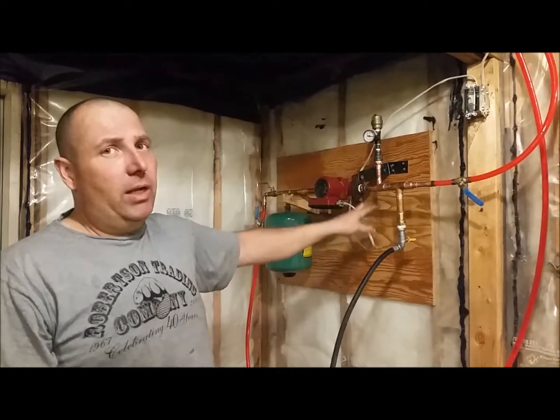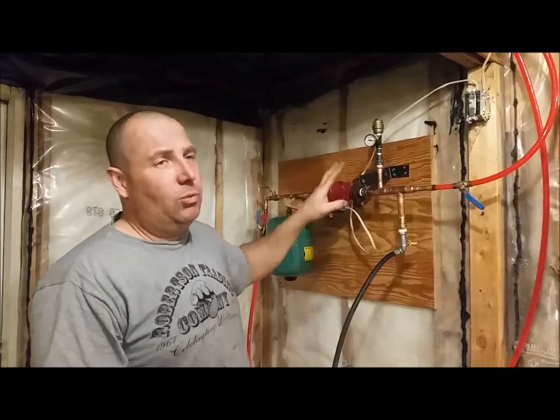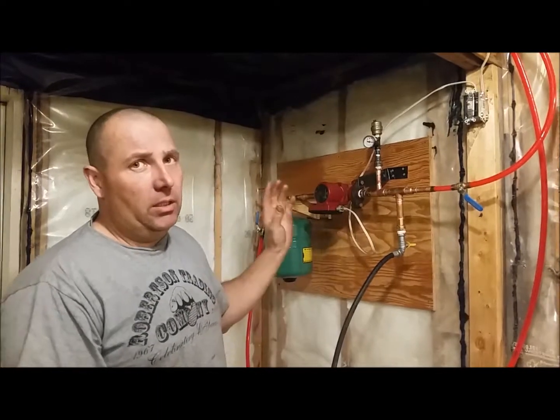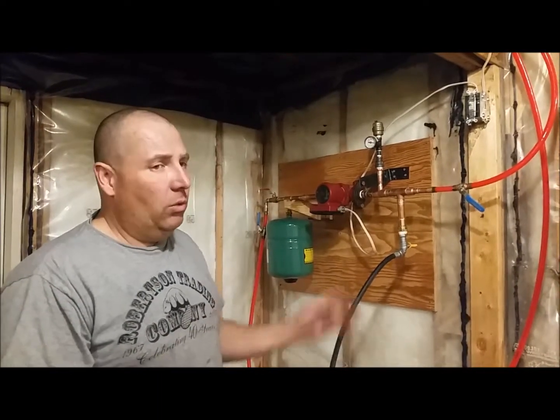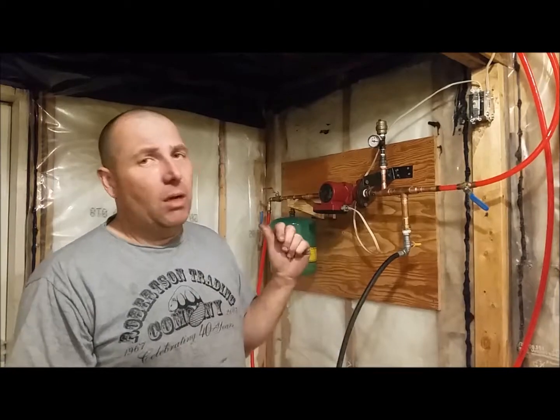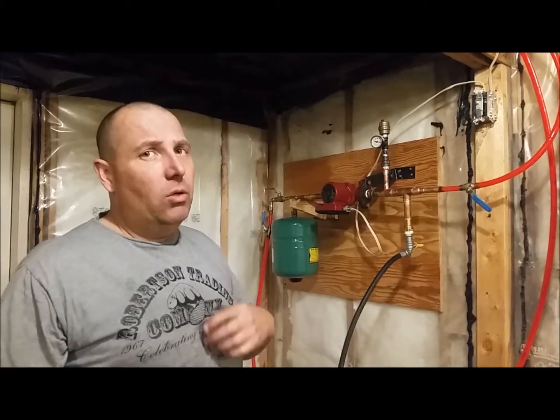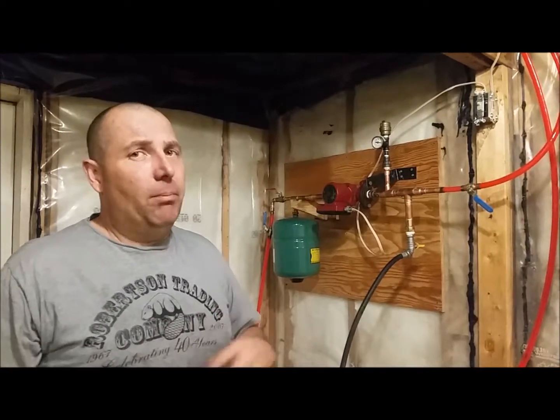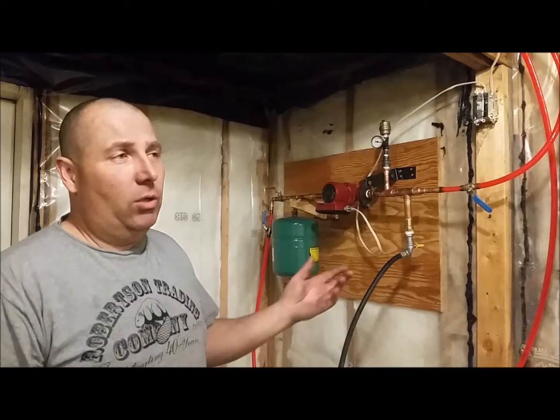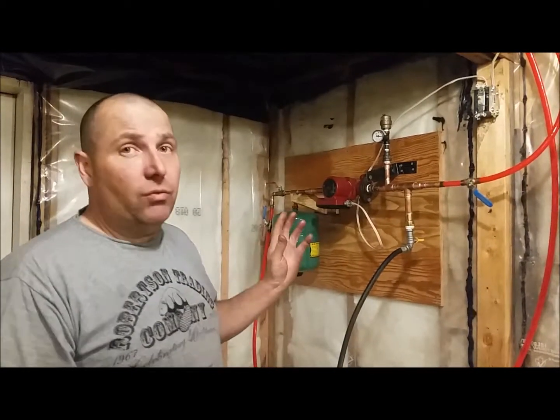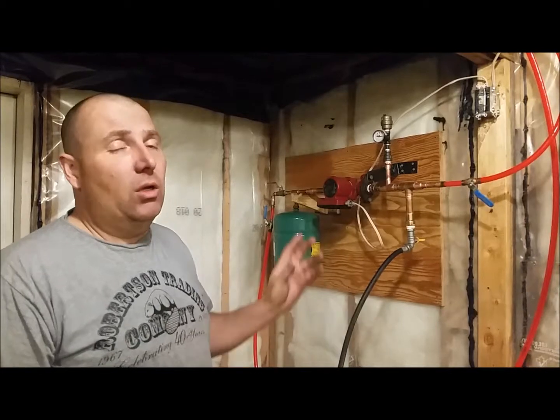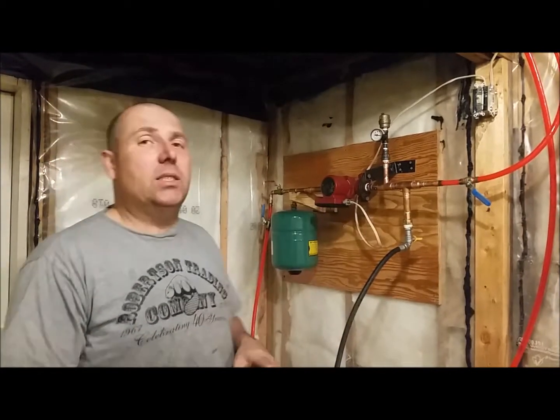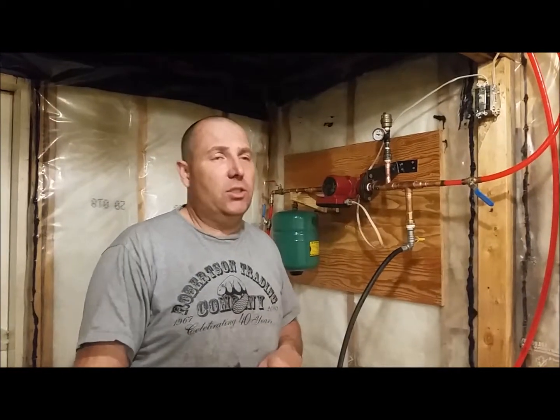So it is a direct circulating system, which means we don't have a reservoir tank that it would be going into. The water that's going into the floor is coming back out of the floor. The water that's going into the heat exchanger and then back out of the heat exchanger goes back into the floor. So there's no big water reservoir to maintain heat. The only heat that's going into the floor is the heat that's actually coming off the heat exchanger.